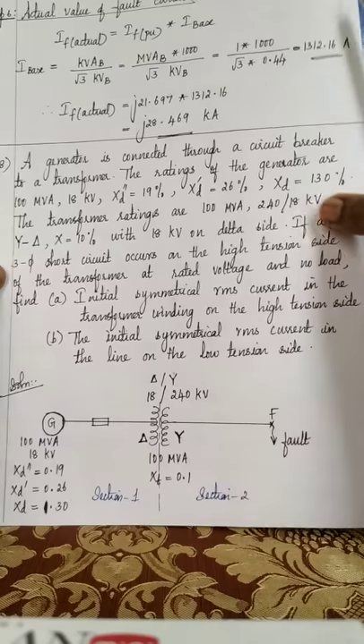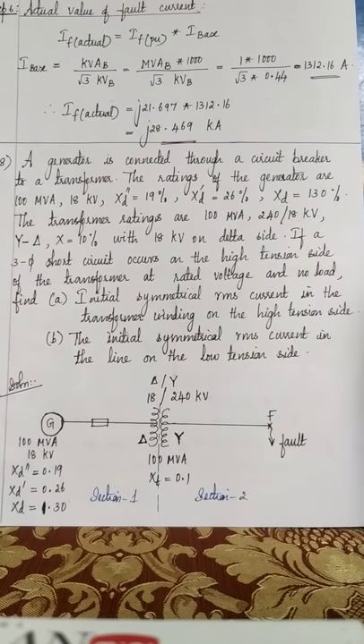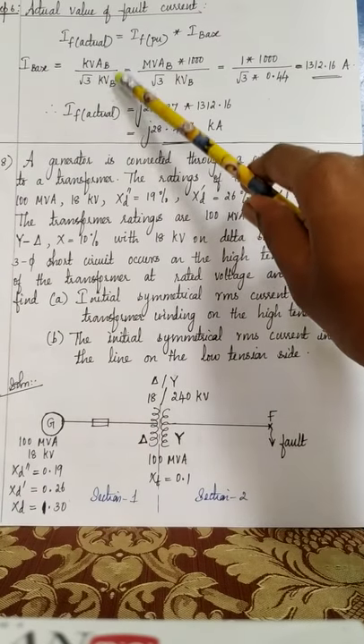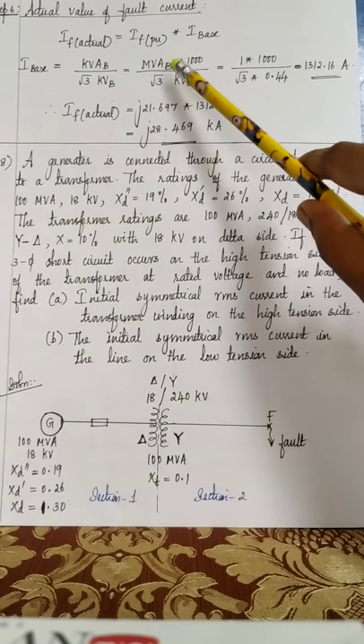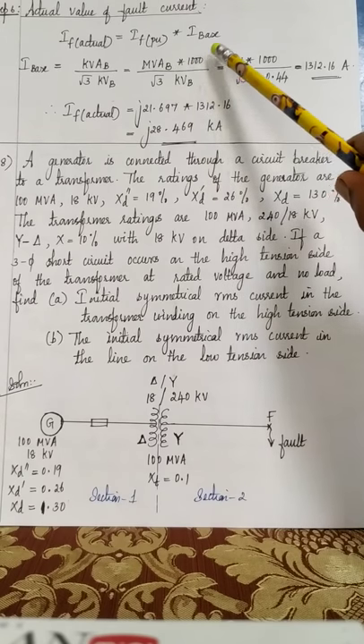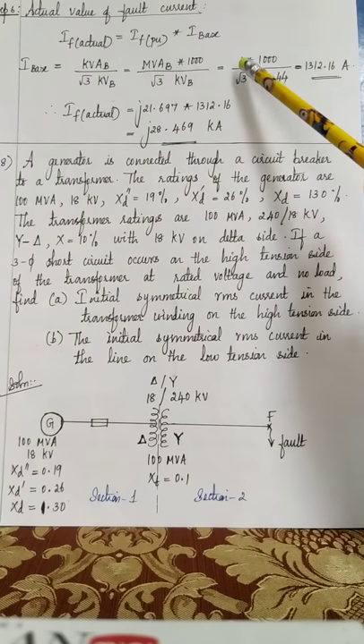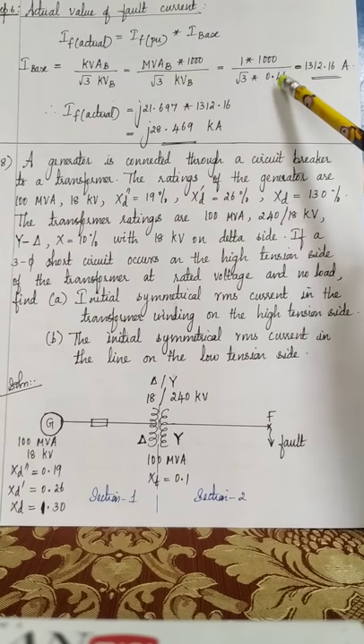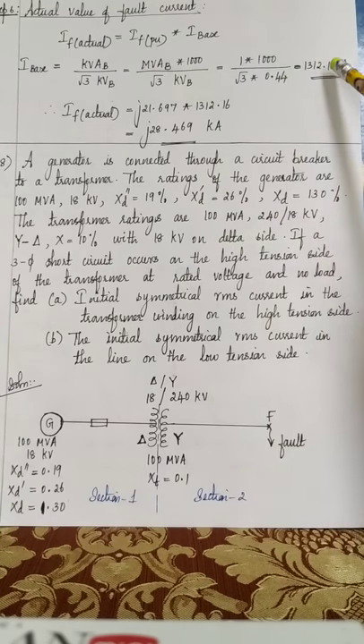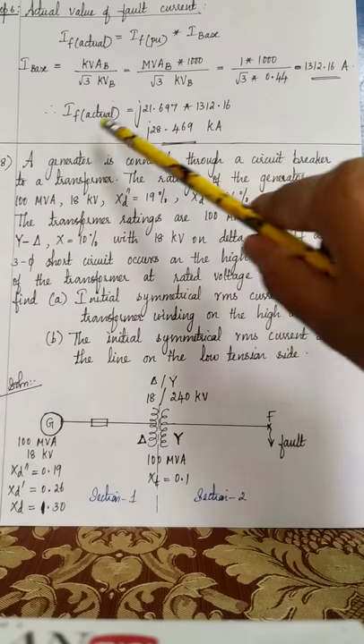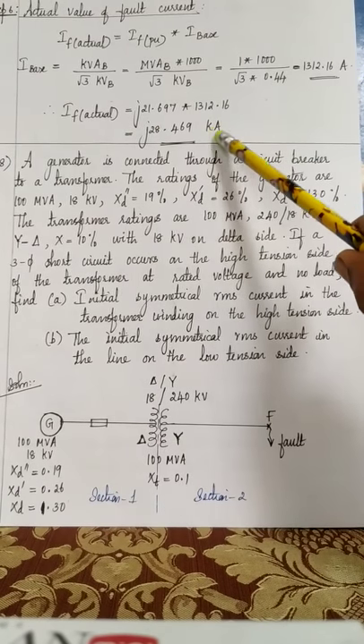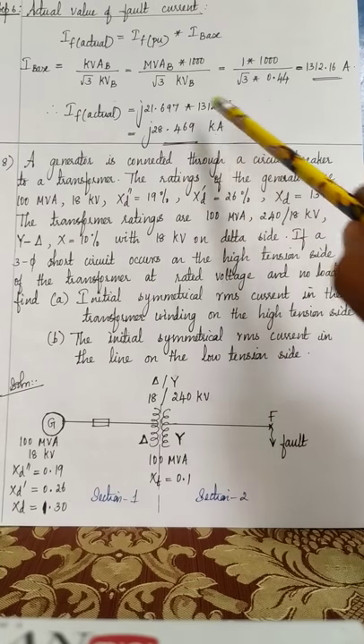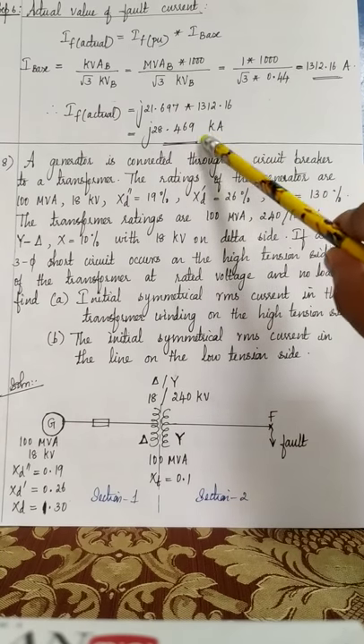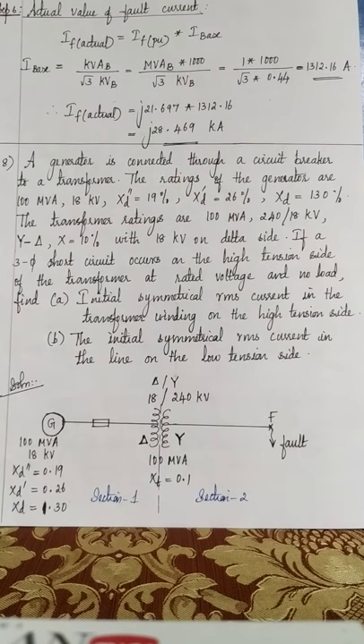Then step 5, to calculate the actual value of fault current. For that, we need the base value, KVAB by root 3 KVB. So KVAB can be written as MVAB into 1000. So what is MVAB? 1 MVA, the generator rating is the common base. What is KVB? 0.44. So we got the base value of current. Now calculate the actual value. I have written it in kilo amperes. If you take only the magnitude, it is 28.469 kilo amperes.